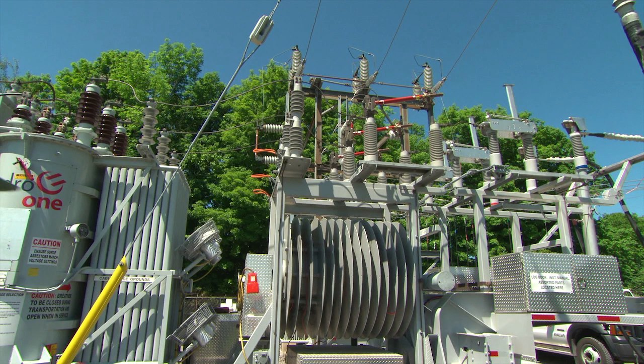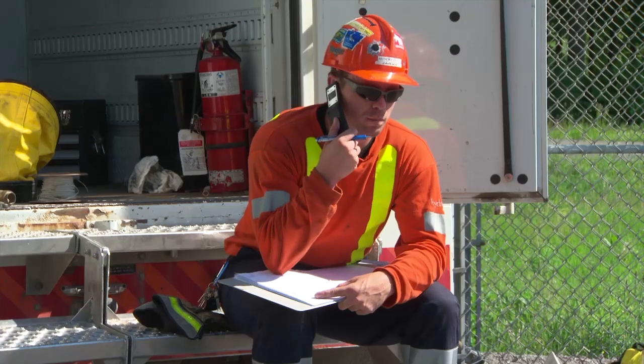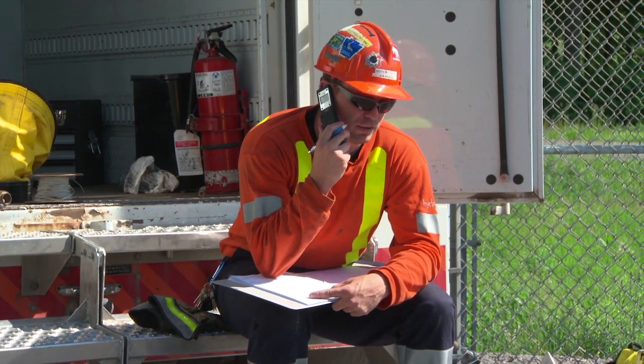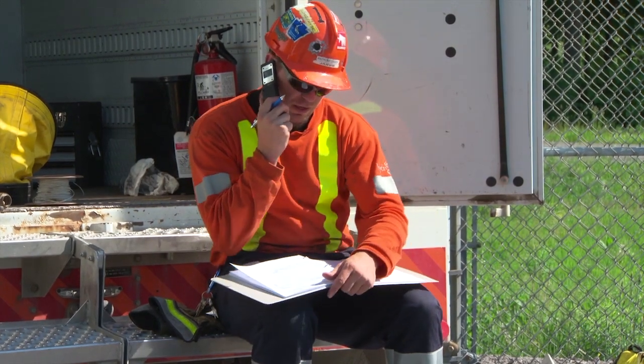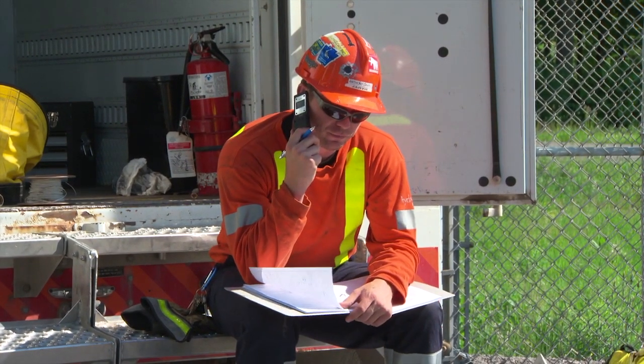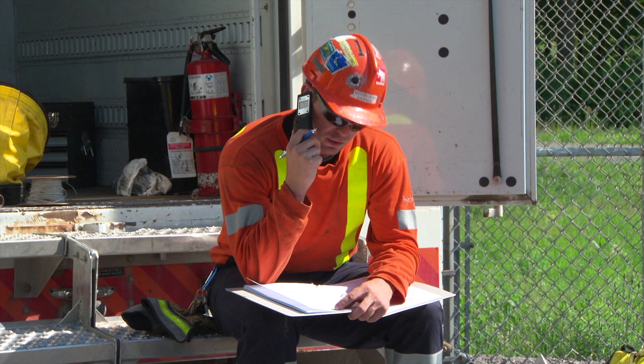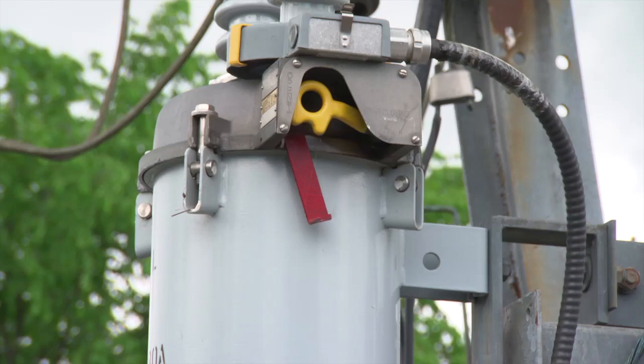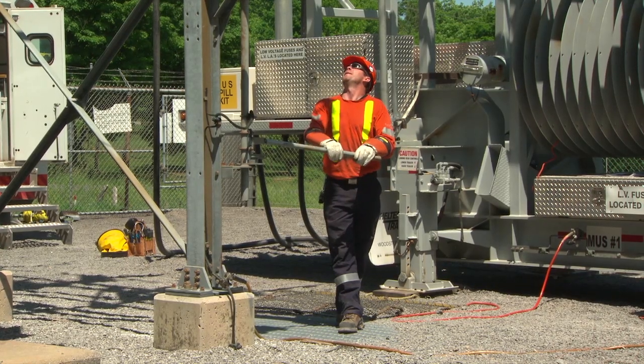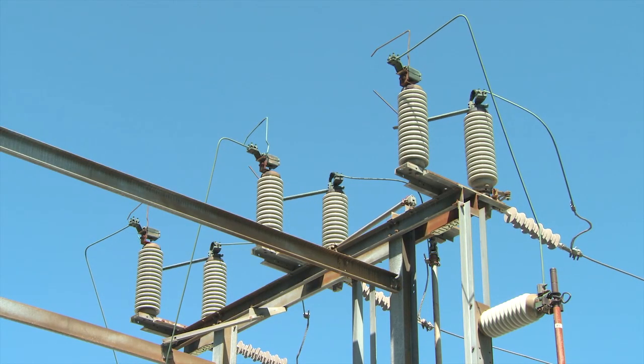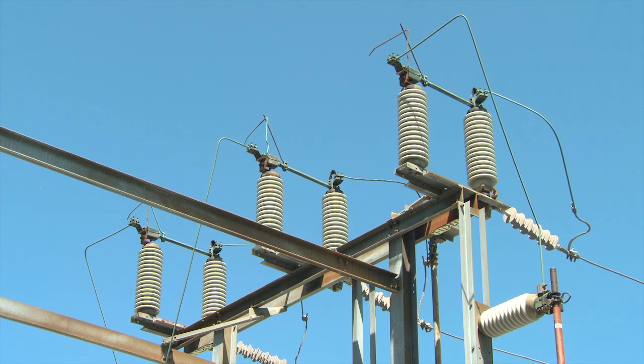We will now look at the steps for removing MUS1 from service. Prepare an OTO for switching the DS into service and switching the MUS out of service. Obtain a hold-off on the 44 kV circuit. Check that the DS reclosers are open and in the non-reclosing position. Close the station high voltage switch. This will put the station back on potential.